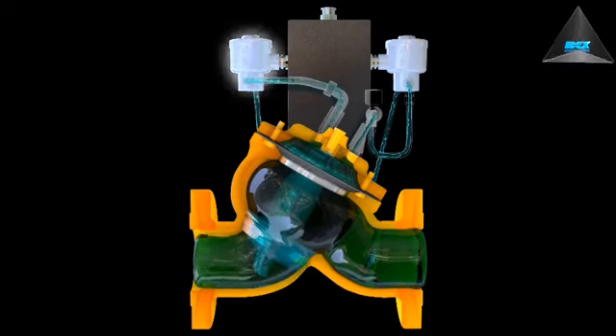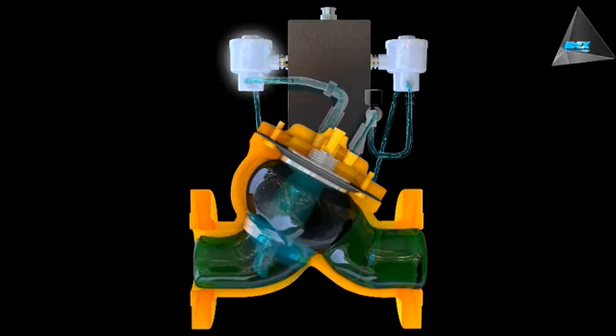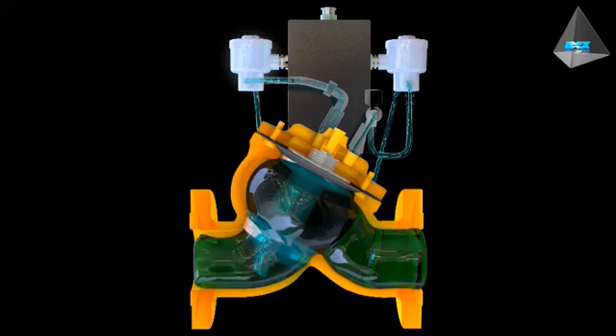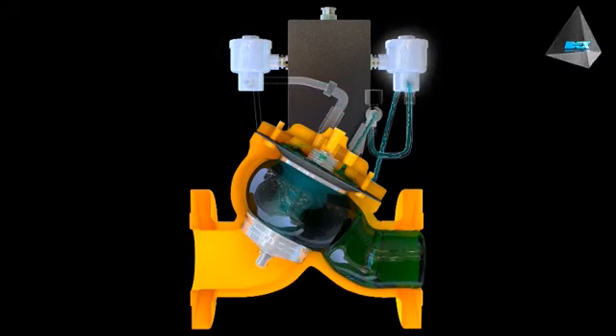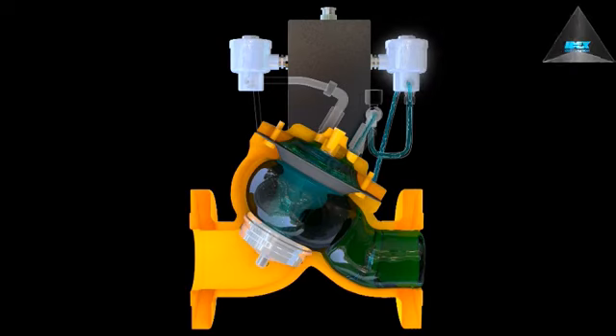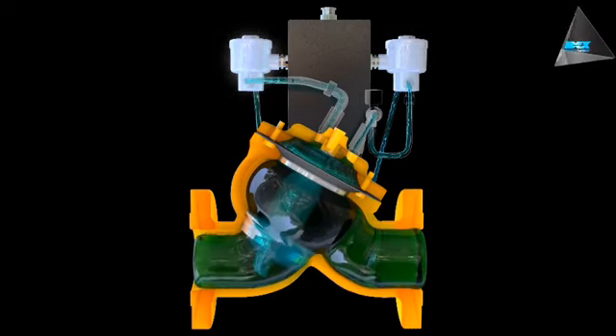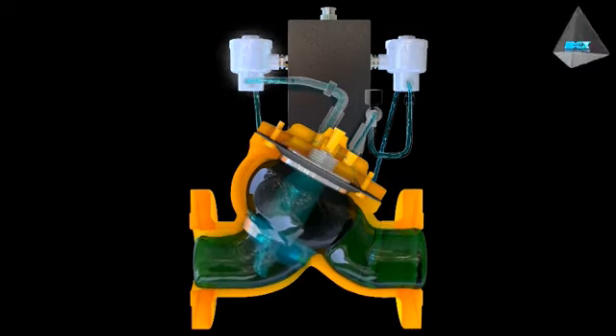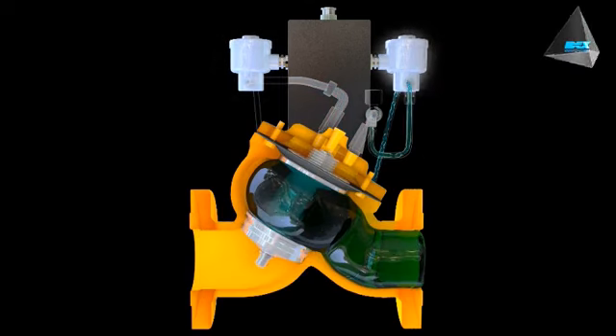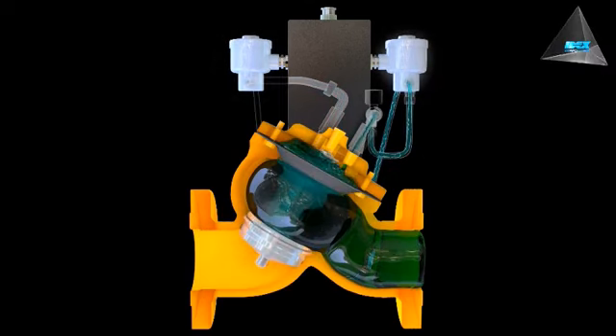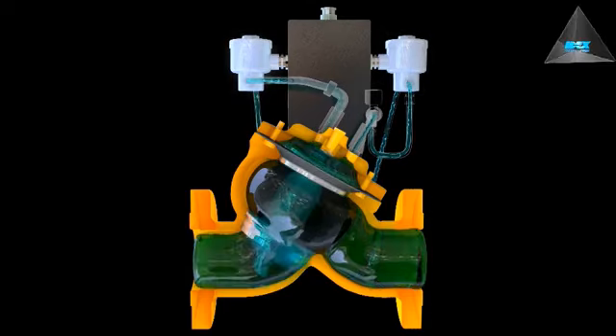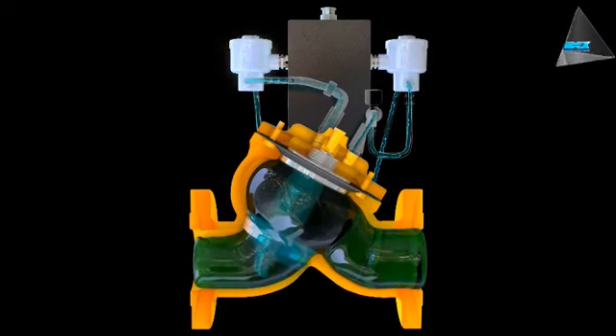Conversely, de-energizing both solenoids allows high upstream pressure to close the valve. Energizing the NO solenoid locks fluid in the valve cover, which locks the valve in a fixed position to maintain a constant flow rate. Whenever a change in flow rate takes place, the flow controller signals the appropriate solenoid to open momentarily to readjust the flow rate to its set value.